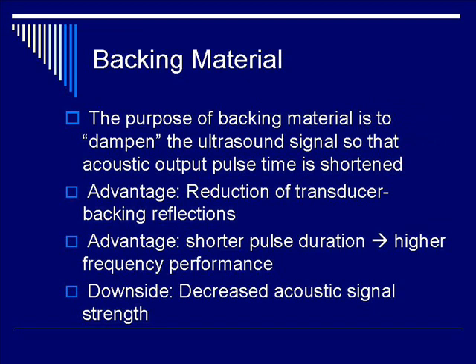The reduction of the pulse time gives you a higher frequency performance, as well as a reduction of the transducer backing reflections. On the other hand, the downside is that your acoustic signal itself has decreased signal strength.